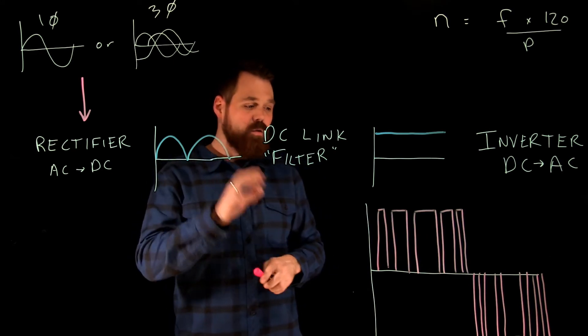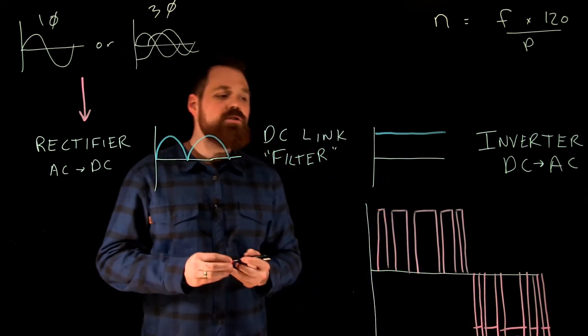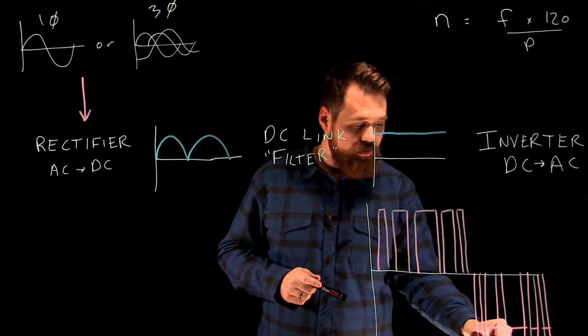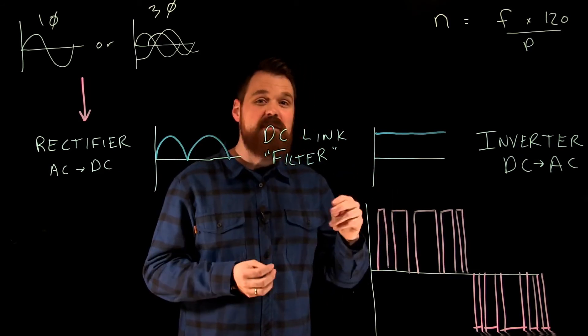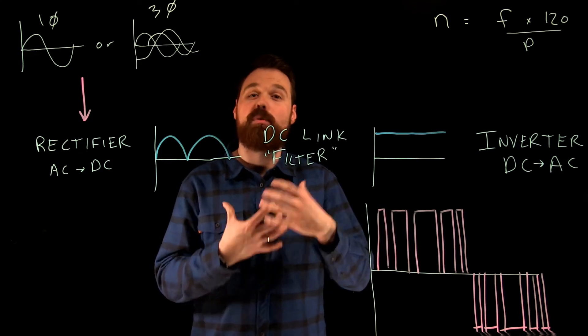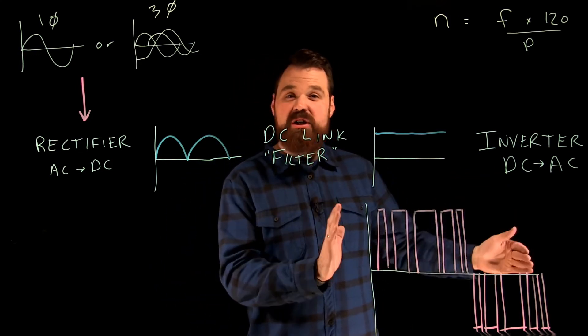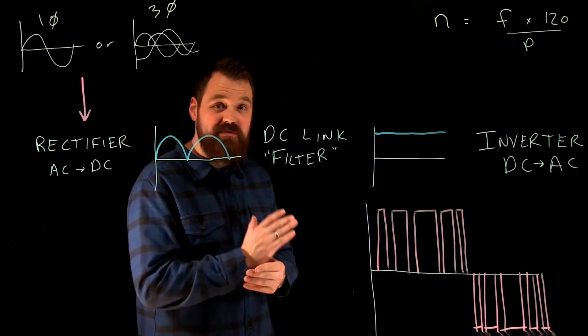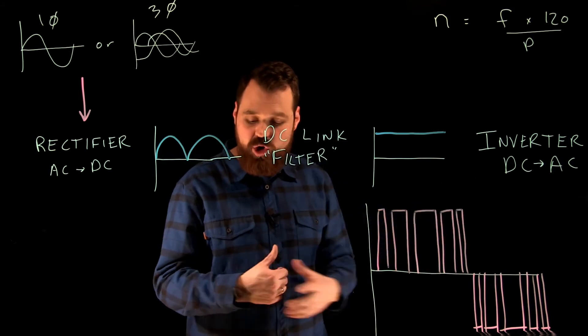We're talking very, very short pulses, very quick—sometimes 1000, 2000, 3000 times per second we're switching this on and off. The speed at which we switch it is called the carrier frequency of a VFD. So it's usually thousands of hertz, thousands of times a second it can turn on and off.